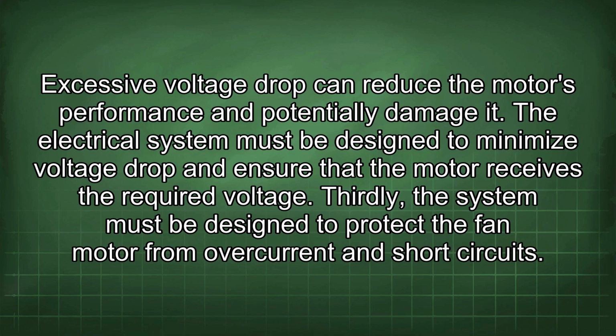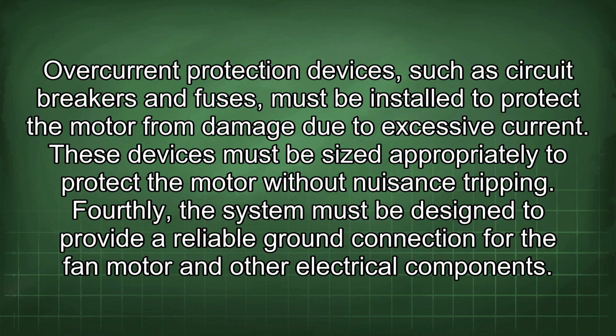Thirdly, the system must be designed to protect the fan motor from overcurrent and short circuits. Overcurrent protection devices, such as circuit breakers and fuses, must be installed to protect the motor from damage due to excessive current. These devices must be sized appropriately to protect the motor without nuisance tripping.